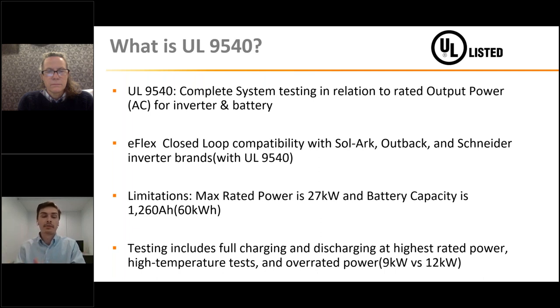The eFlex has closed-loop compatibility with Sol-Ark, Outback, and Schneider, with this UL9540 listing of the inverter and battery being tested together. There are some limitations to be aware of with UL9540, including the max rated power being 27 kW and the maximum battery capacity being 1,260 amp hours, which pencils out to roughly 60 kilowatt hours.